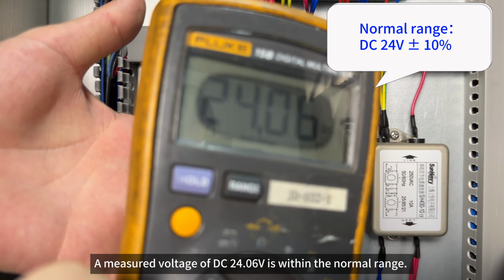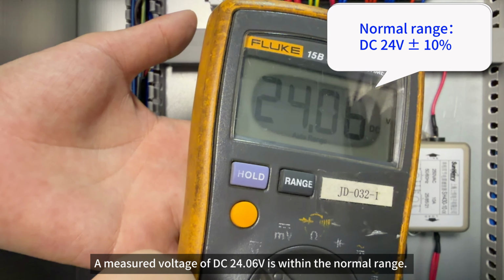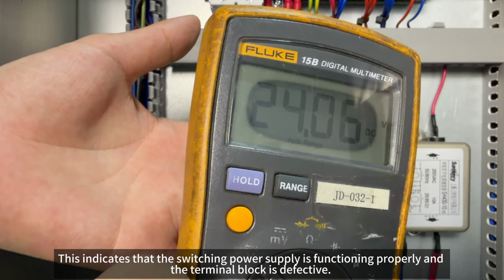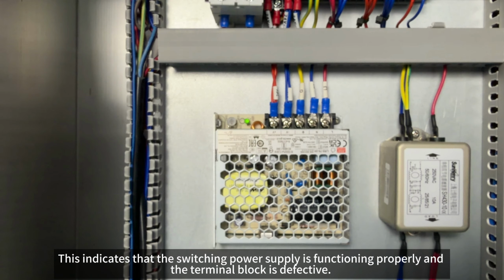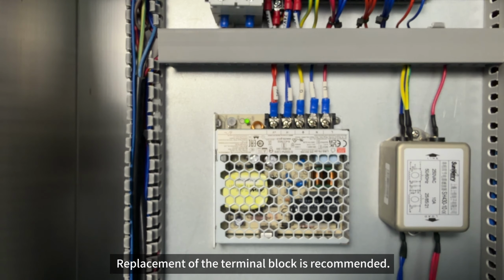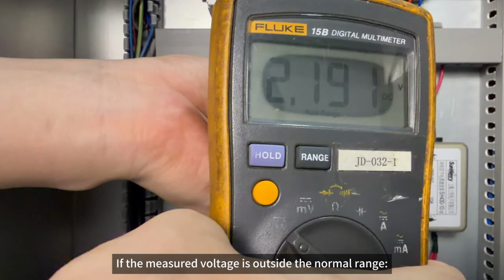A measured voltage of DC 24.06 volts is within the normal range. This indicates that the switching power supply is functioning properly and the terminal block is defective. Replacement of the terminal block is recommended. If the measured voltage is outside the normal range, the switching power supply should be replaced. If the terminal block remains abnormal after replacing the switching power supply, the terminal block should also be replaced.